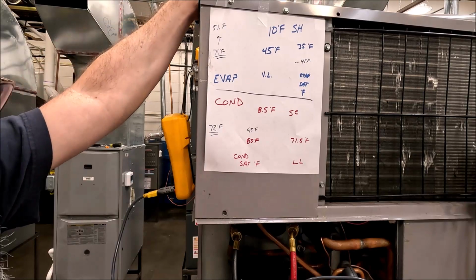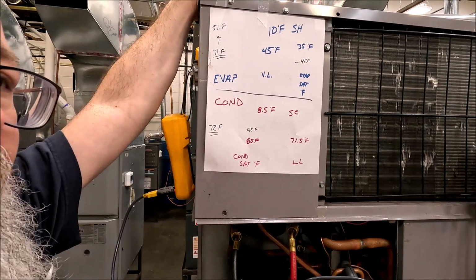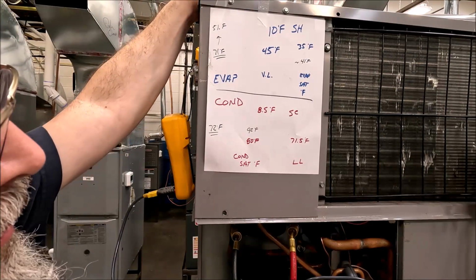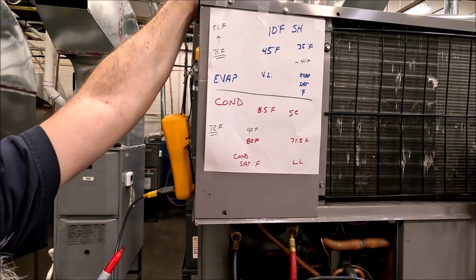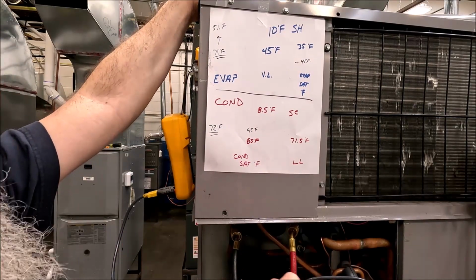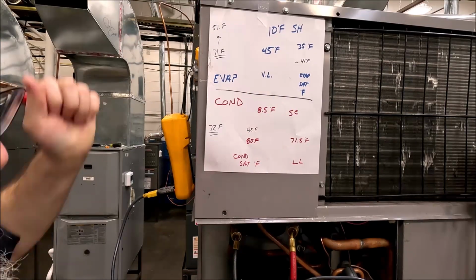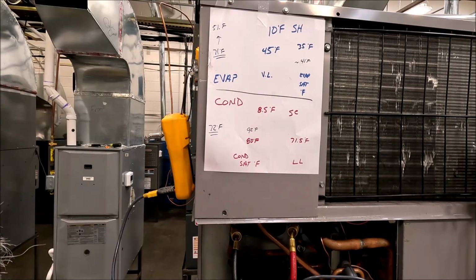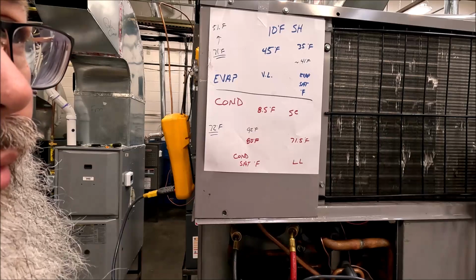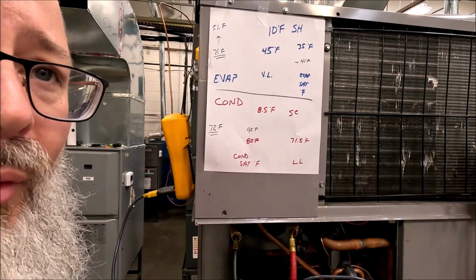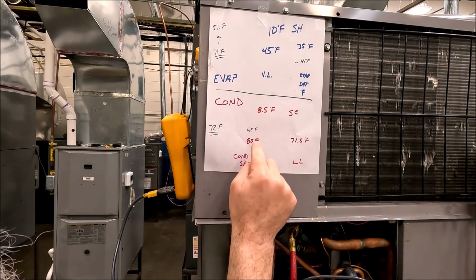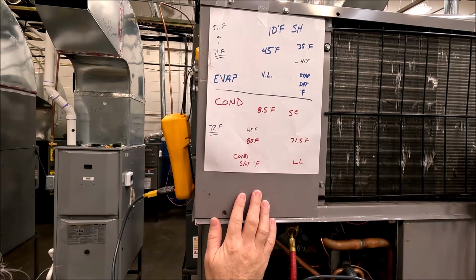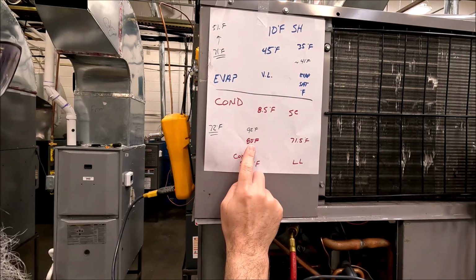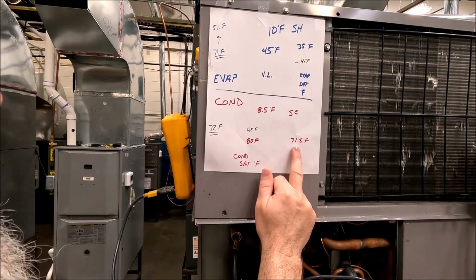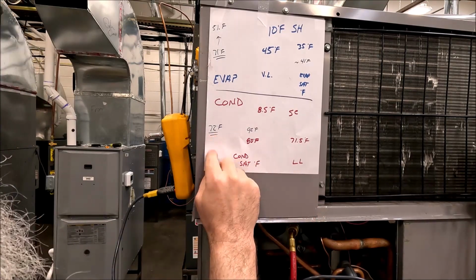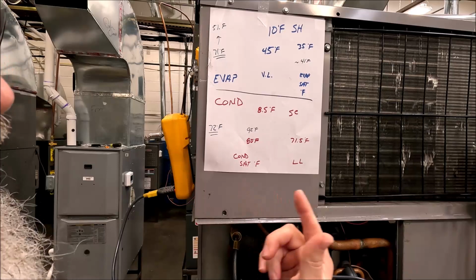Okay, so don't use the number from the discharge line. It doesn't do you any good. So 8.5 degrees of subcooling. Is that good? Is that bad? I don't know. Is 10 degrees of superheat bad? The generic rules of thumb are going to tell you 8 to 12 degrees of superheat, you know, 8 to 12 degrees of subcooling. You have to do all your readings. So we've got pressures to go with that saturation temperature. We've got line temperatures. We've got air temperatures. This is what you have to do to get it done.